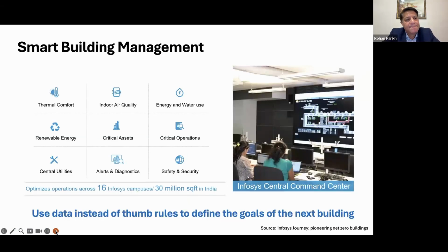Before I stop, I want to stress the importance of the building management system. Infosys has an active central command team that watches alarms across all campuses and geographies. They have so much data, and someone is watching the alarms and fixing issues. This is key, because sensors tend to drift and things do go wrong—a VAV box can fail, small motors can fail.